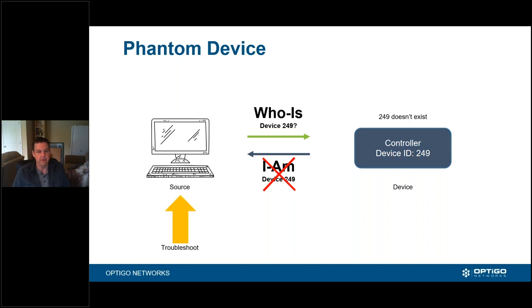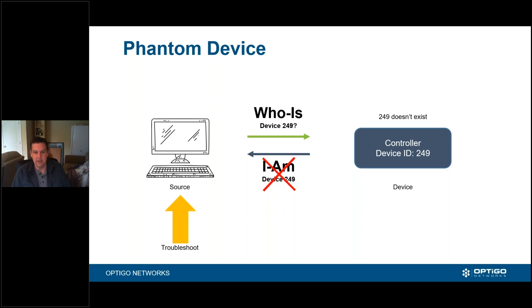One reason could be that the device shouldn't exist. Maybe somebody accidentally put in a bad graphic link or put in some piece of data exchange under the source, asking for this device when it shouldn't even be there. Maybe some code was obsoleted or decommissioned and something was still left inside of the database — this is what we call a phantom device. If you see a device sitting on your BACnet front end with a little red X, that's a good indication the device isn't communicating. Start with the front-end BMS, because Visual BACnet can only tell you something's asking for this device and it's not responding.